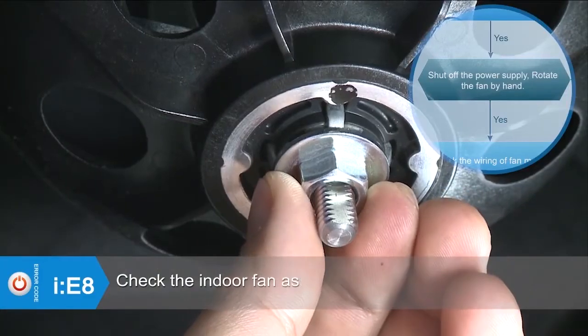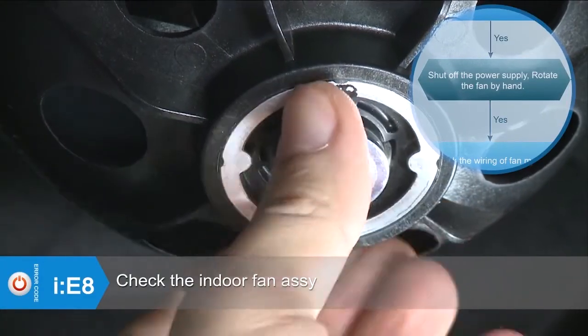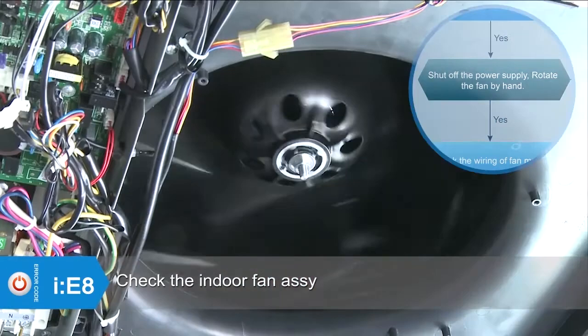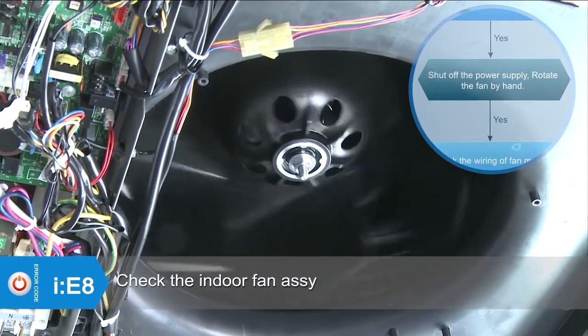Rotate the fan blower by hand. Check whether the fan is blocked or rotating abnormally, and whether the screws which fix the fan have been tightened.